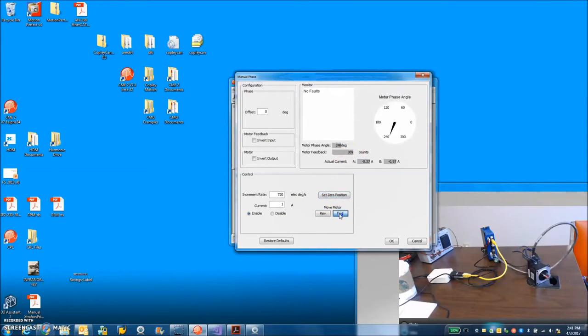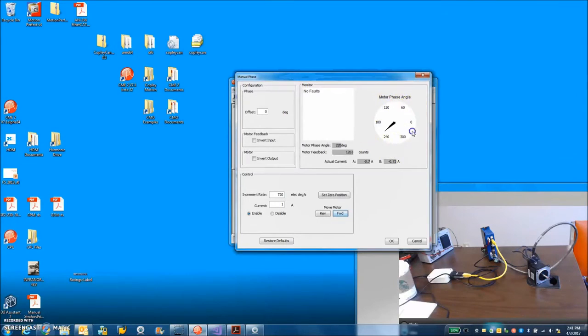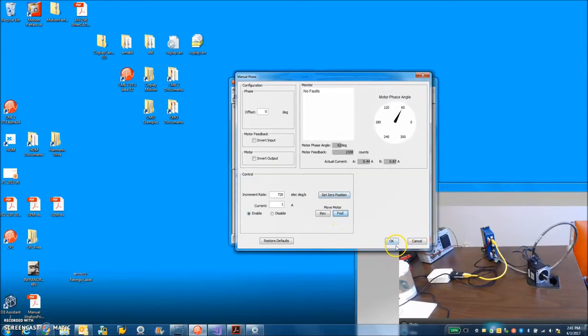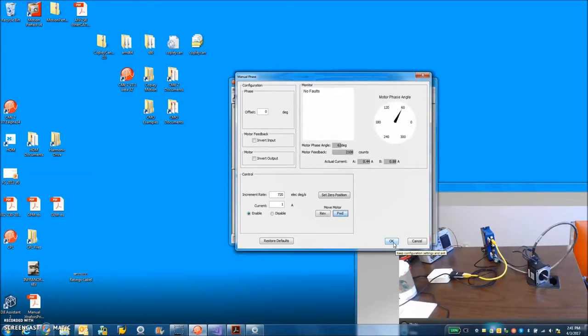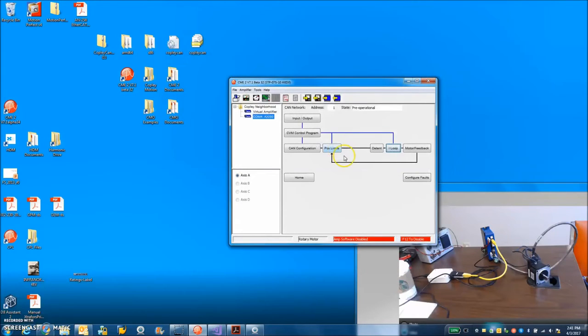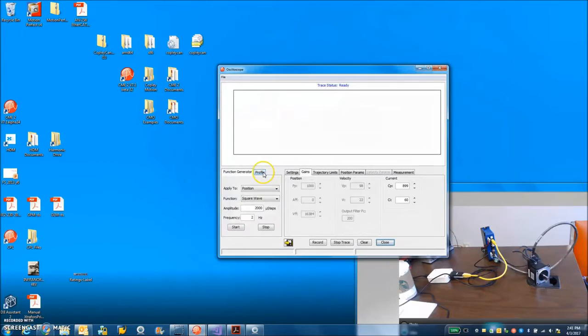I got clockwise of my motor here going forward and as I rotate the current vector everybody gets a turn to deliver current plus or minus an amp and my counts go forward. There's about a half a rev. So yeah I got a 4000 count, check that out, and forward positive counts. I don't need to invert the motor feedback so we're good with that.